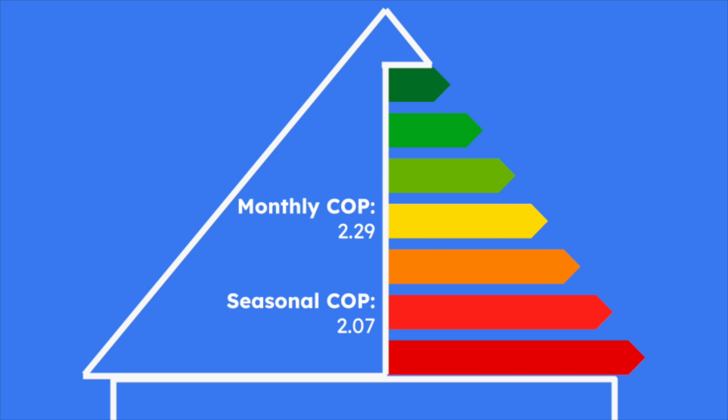When we compare far-infrared to gas, we find that far-infrared has a COP of 2.29 for this month and 2-ish generally over the heating season. This means that for every kilowatt hour of electricity we'd need for far-infrared heating, we'd need roughly double that for gas. This has been calculated by forecasting the gas usage for each day over this heating period, based on the historical correlation between gas usage and outdoor temperature. I've described this process in more detail in the video looking at the December and January usage, link in the comment below.